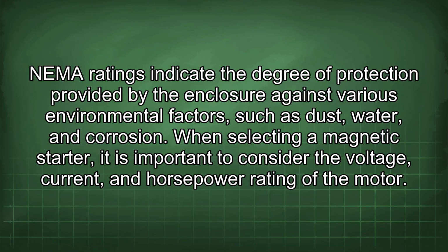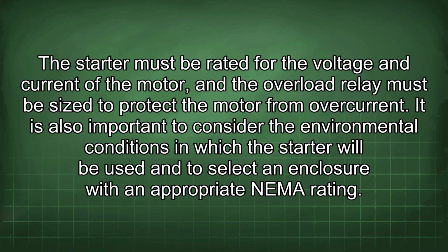NEMA ratings indicate the degree of protection provided by the enclosure against various environmental factors such as dust, water, and corrosion. When selecting a magnetic starter, it is important to consider the voltage, current, and horsepower rating of the motor. The starter must be rated for the voltage and current of the motor, and the overload relay must be sized to protect the motor from overcurrent. It is also important to consider the environmental conditions in which the starter will be used and to select an enclosure with an appropriate NEMA rating.